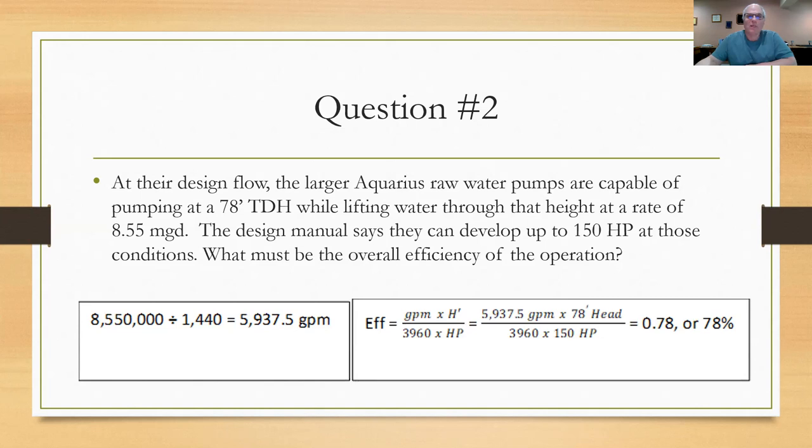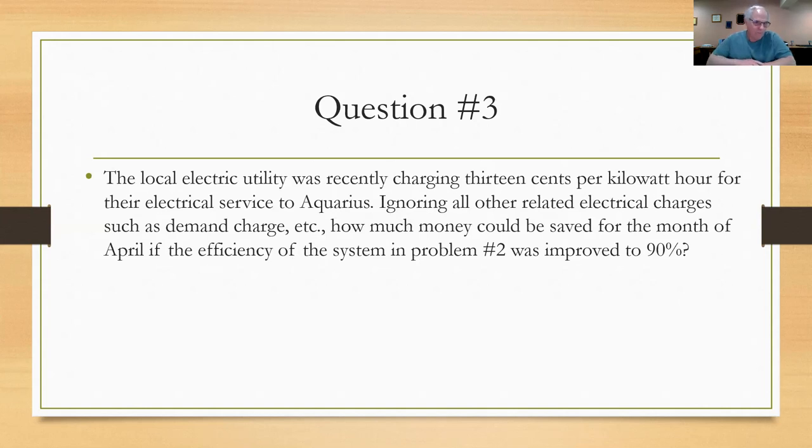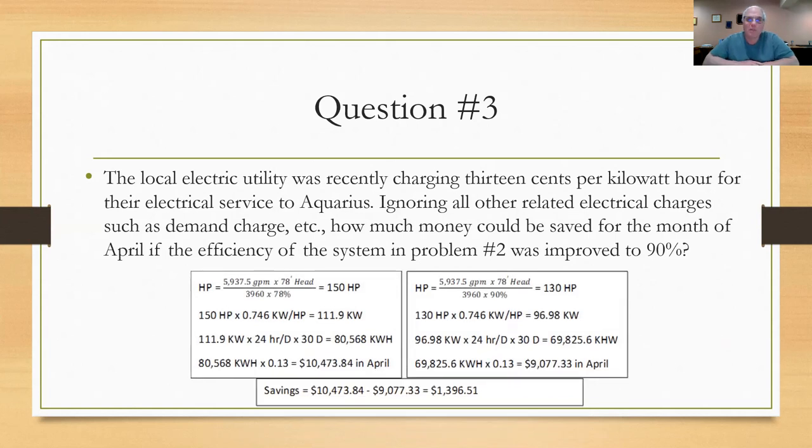We figured out at max flow and at the total dynamic head, we're at 78%. This question says, if the local electric utility is charging you 13 cents per kilowatt hour for their electrical service, and if you ignore all the related electrical charges such as demand charges, how much money could you save in the month of April if the efficiency of the system in problem number two was improved to 90%? Remember, we calculated 78% there. If we were able to make that pumping system 90% efficient, how much money could we save in April? Well, we know that April is a 30-day month. You can attack this two different ways, and I'm going to do this problem the long way. The first thing I'm going to do is figure out the cost in April to operate that system at the 78% efficiency, and I'll do it for the 90% efficiency and compare the cost.